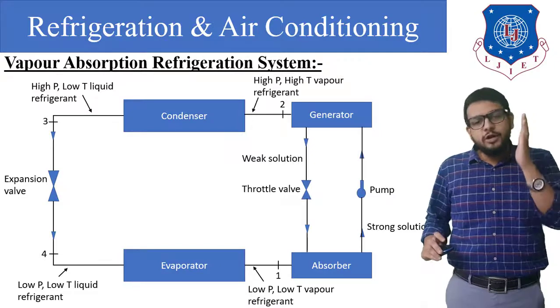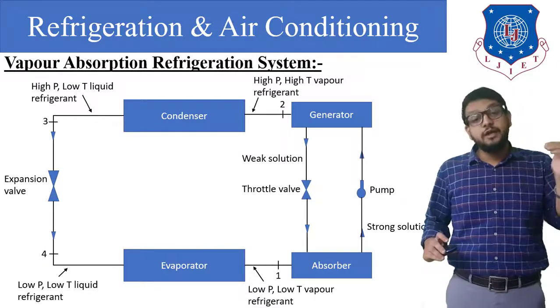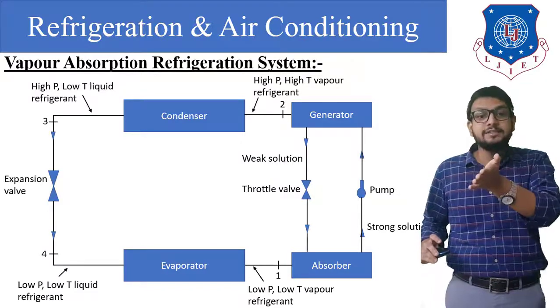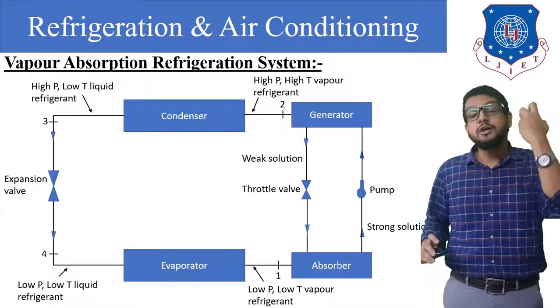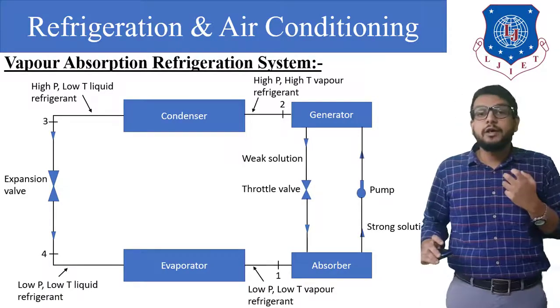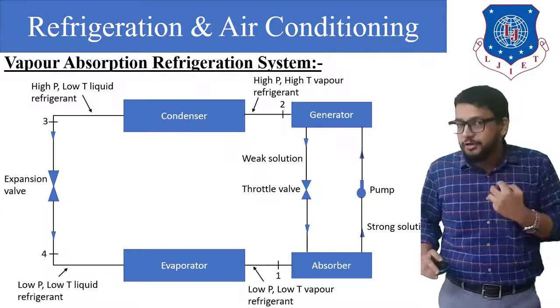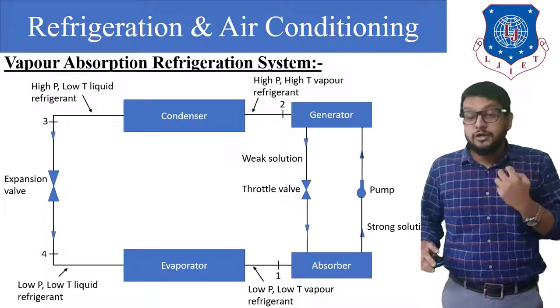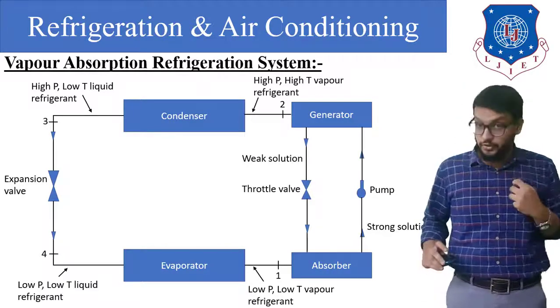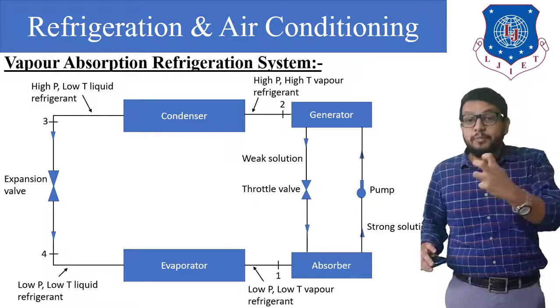Starting from point number four: low pressure, low temperature liquid refrigerant enters the evaporator, absorbs heat energy from the freezing compartment, gets vaporized, and at the exit of the evaporator — point number one — we have low pressure, low temperature vapor refrigerant. This vapor refrigerant enters the absorber, where it is absorbed by the cold water, forming a strong solution of ammonia in which the ammonia content is much higher. That strong solution is then sucked by the pump.